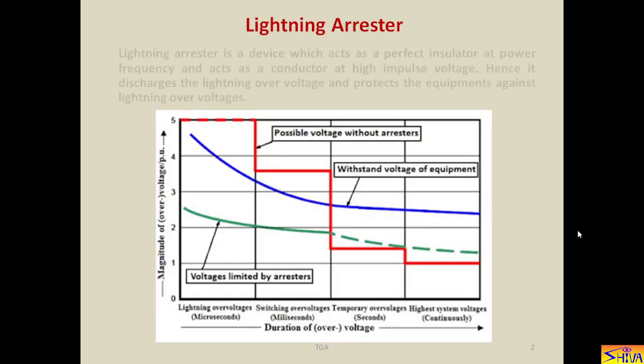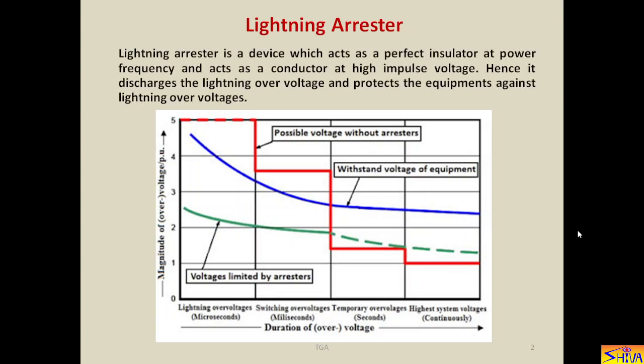So let us see what this lightning arrestor is. A lightning arrestor is a device which acts as a perfect insulator at power frequency and acts as a conductor at high impulse voltage. Hence, it discharges the lightning over voltage and protects the equipments against lightning over voltages. So basically, a lightning arrestor is nothing but a device which protects the electrical equipments from lightning over voltages. So it must act as a perfect insulator at power frequency and it must provide a path of low impedance when there is lightning over voltage. Lightning over voltage means impulse voltage. In the system it is installed before the equipment being protected in the substations and switchyard.